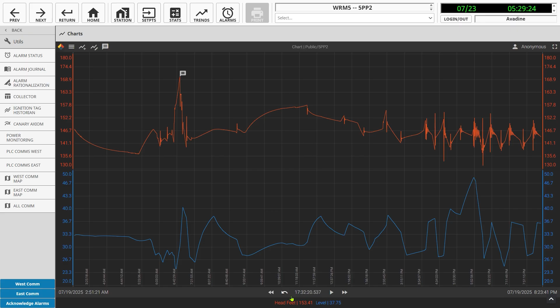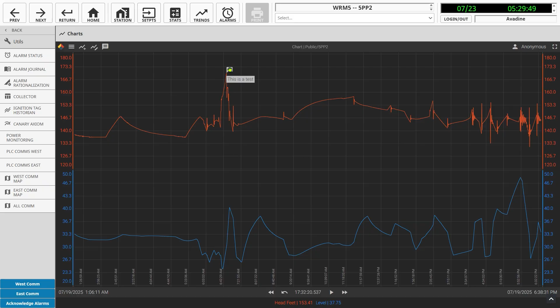Since going live, the district has experienced no unplanned comm fail events. Operators now have real-time visibility into tank levels, pump status, and VFD performance. They can respond instantly instead of waiting for the next data cycle. Each avoided field reset saves 2 to 3 hours of technician time.